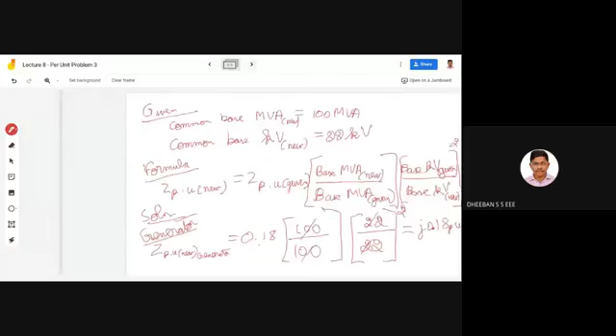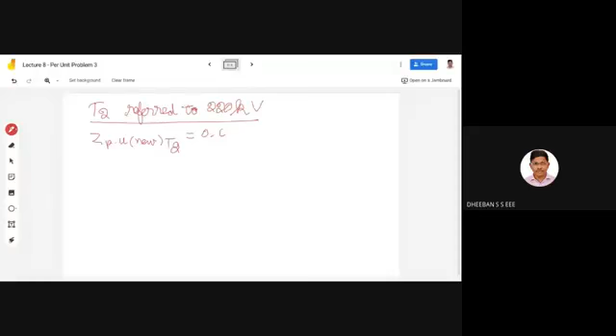Okay, so after this we will be moving towards the T2 referred to 220 kV. Okay, and for this Z per unit new of T2 will be equal to 0.06 into 100 by 40 into 220 by 220. So this is nothing but your revised kV new for your T1. Okay, so that's the value over here, the whole square.